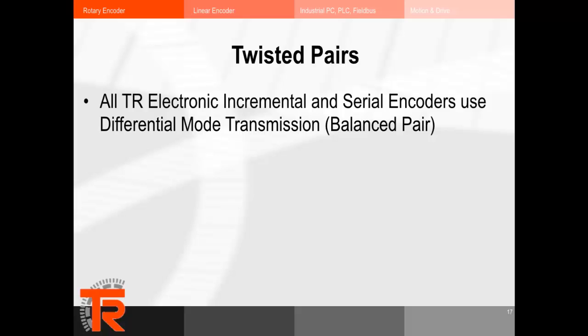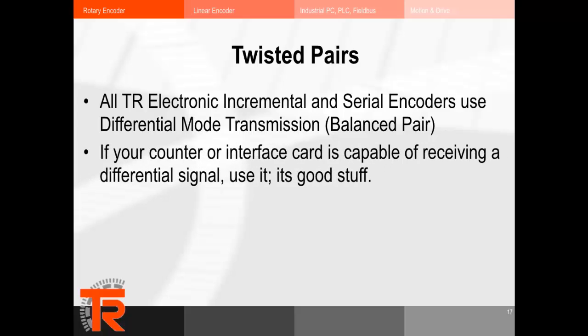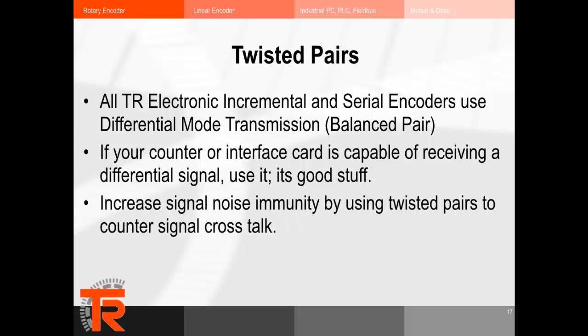Let's talk about twisted pair. All TR Electronic incremental and serial encoders use differential mode transmission, or balanced pair. If your counter or interface card is capable of receiving a differential signal, use it — it's good. Twisted pair increases signal noise immunity by countering signal crosstalk. If you use a cable with multiple non-twisted pairs, one pair can induce crosstalk into another, and it's additive along the length of the cable, getting worse the longer the cable is. Twisting the pairs counters this effect because with each half-twist, the wire nearest to the noise source is exchanged, minimizing crosstalk.